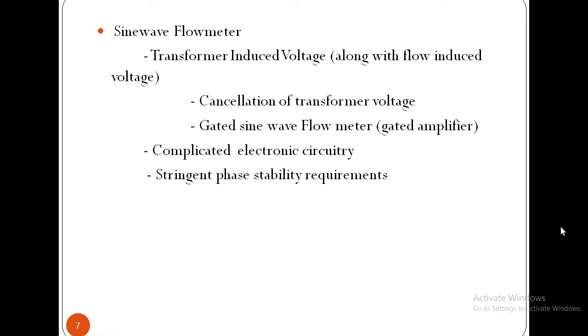An alternative method to eliminate the transformer induced voltage in sine wave flow meters is by using a gated amplifier. The function of this amplifier is to permit the amplification of the signals only during the portion of the cycle where flow induced voltages are maximum and the transformer induced voltages are minimum. By this method, the artifact voltage is prevented from getting amplified. This instrument is known as gated sine wave flow meter.